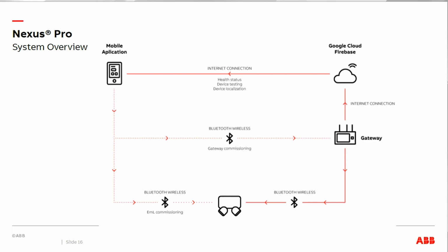The Nexus Pro system uses Bluetooth technology to communicate between the fixtures as well as back to the gateway, shown here in the bottom right-hand corner of your screen. The emergency lighting luminaires communicate with each other using a technology called Bluetooth Mesh, or BTM for short. This means every single emergency lighting fixture acts as both a transmitter and receiver of all information being transmitted, whether it be testing information, scheduling, and so on. This makes the system a lot more robust, since each fixture can transmit testing information to another unit, ultimately making its way back to the gateway. This eliminates hardwired or hard-coded communication paths back to either a router or a gateway.